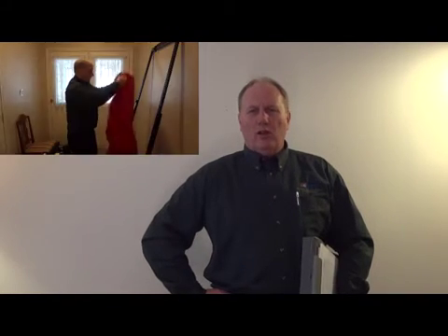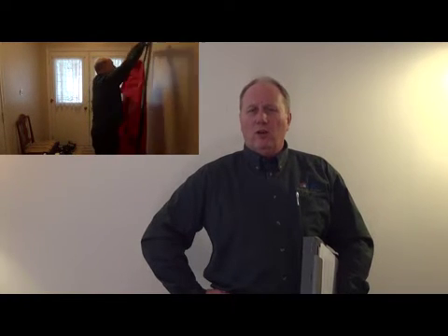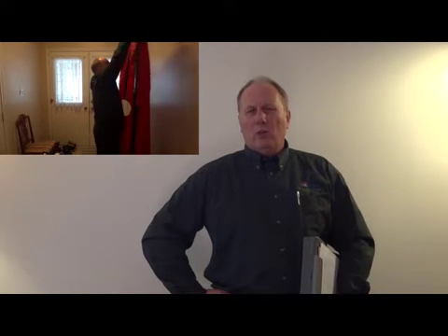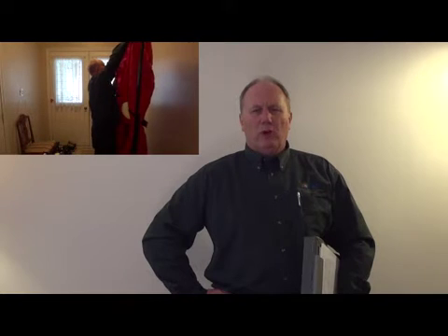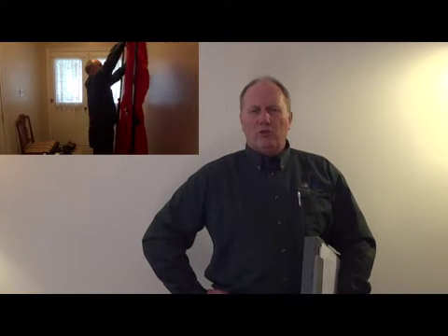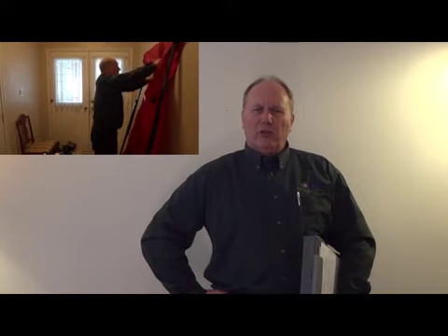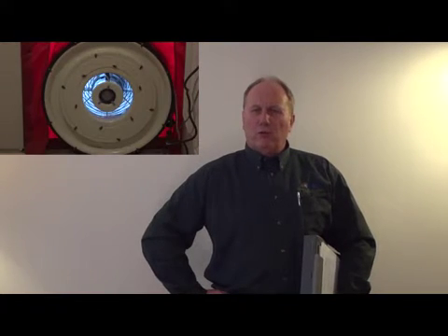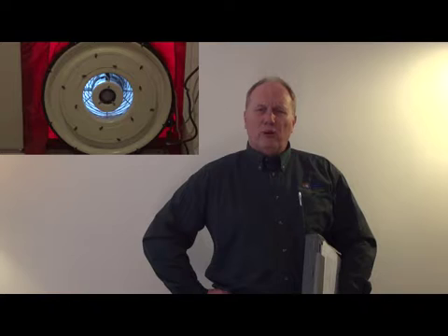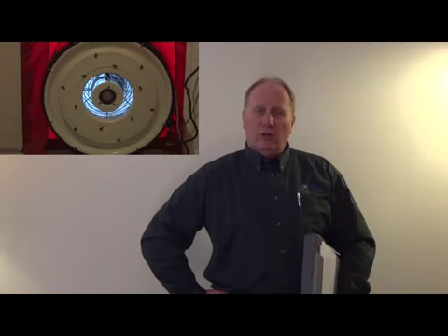Hi there. Today we're going to be doing an energy audit on this home, which is going to involve an air infiltration test using a blower door system, and also a heat load calculation where we'll have to calculate the volume of the home for our calculations. We're going to begin the blower door test by installing the blower door, which is a large frame that goes in an exterior door. It consists of a large fan with multiple rings so that we can control the amount of air that's flowing in or out of the building.